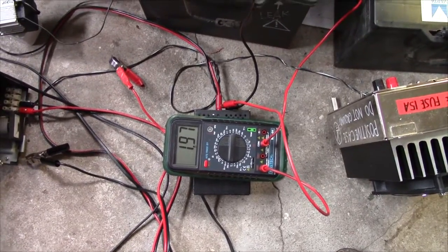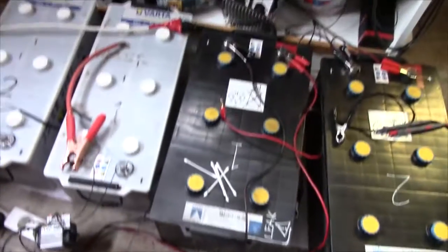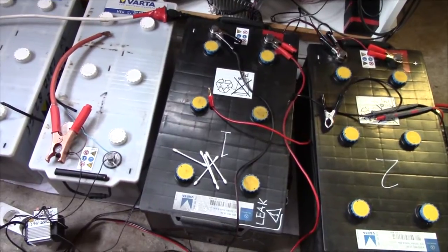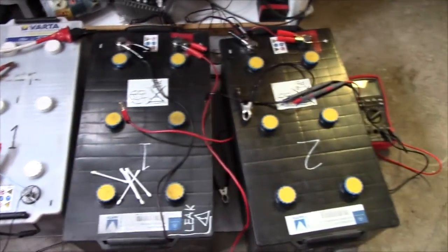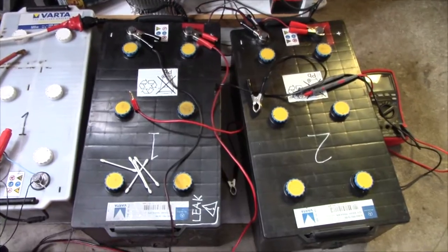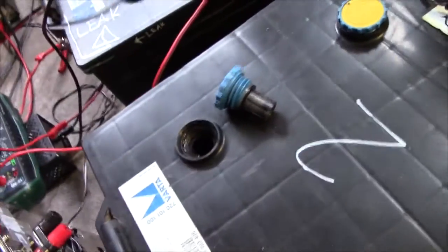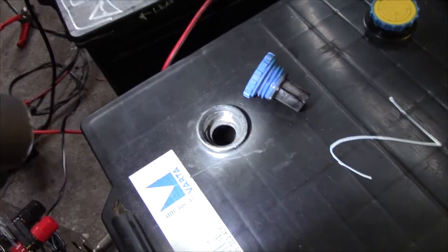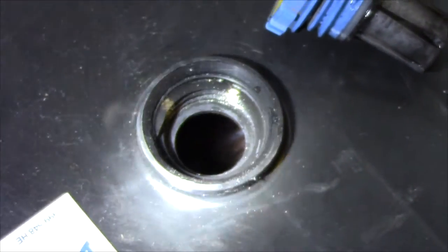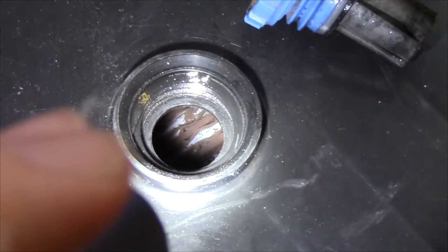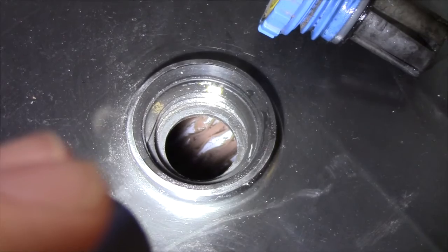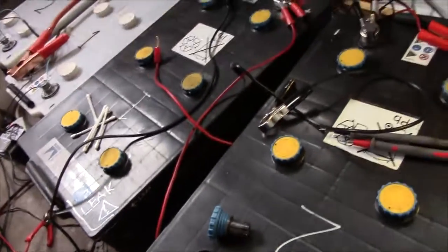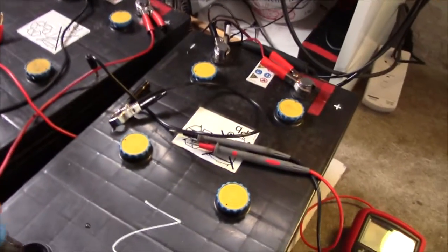Number one has been charging overnight. It's down to about 2 amps and I just had a look in the cells. Really on both the batteries, the sulphate that you can see at the top of the cells is starting to just come off and disappear. You can pretty much just see the grey positive plates there instead of the horrible whitish goop, that crust that was on there when I got them. I think these two are starting to shape up. I don't think I'm going to cycle this one anymore.